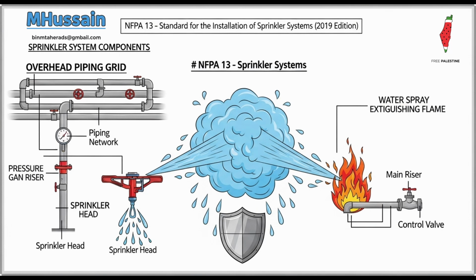Okay, so once everything is installed, the proof is in the performance, right? Through acceptance testing. This is the hydrostatic test. It's the moment of truth, really. All piping that's subjected to system working pressure must be tested at either 200 psi, that's 13.8 bar, or 50 psi, 3.4 bar, in excess of the system working pressure, whichever one is greater. And crucially, that pressure must be maintained for a minimum of 2 hours. That extended hold time is specifically meant to reveal subtle leaks that might not show up instantly under pressure.